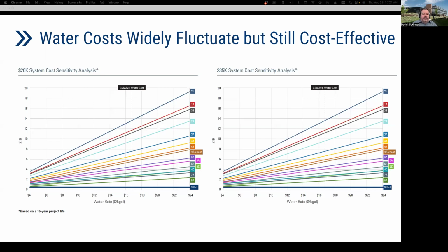On the left side, what is being shown is a $20,000 low-cost AWT system installed, and it's life cycle cost-effective across all 16 climate zones when the combined water and sewer rate is more than $4 per 1,000 gallons. On the right, that's showing a $35,000 higher cost AWT system installed, and that's life cycle cost effective again across all 16 ASHRAE zones when the combined water and sewer rate is more than $8 per 1,000 gallons. So water costs fluctuate widely across the country, resulting in more varied savings, but still cost effective. Next slide, please.